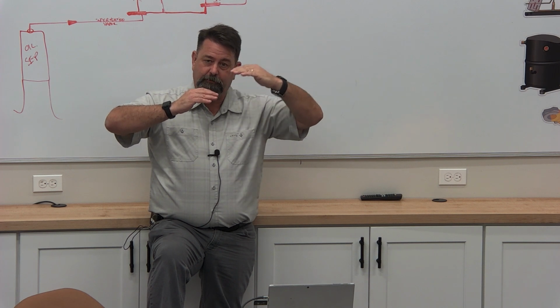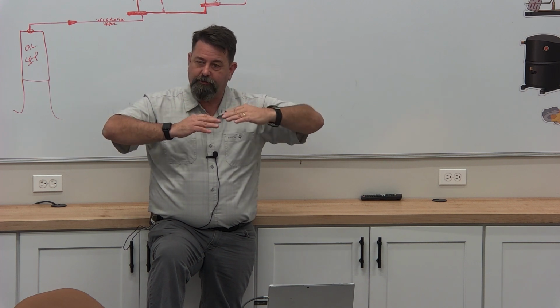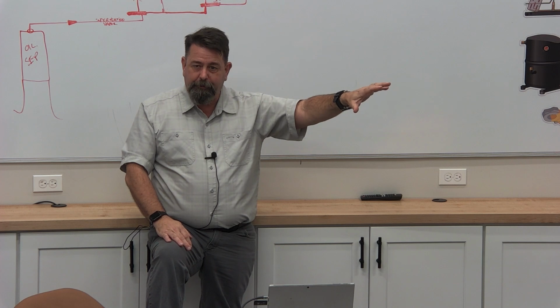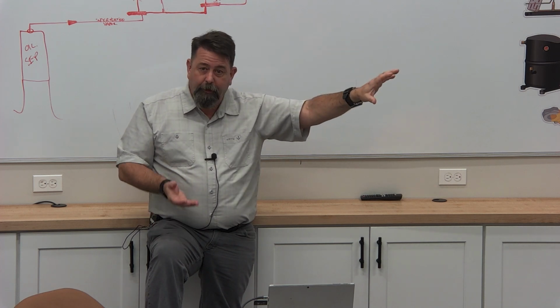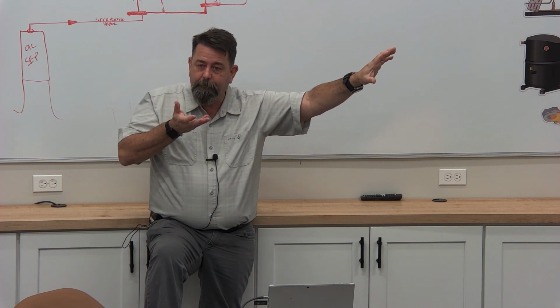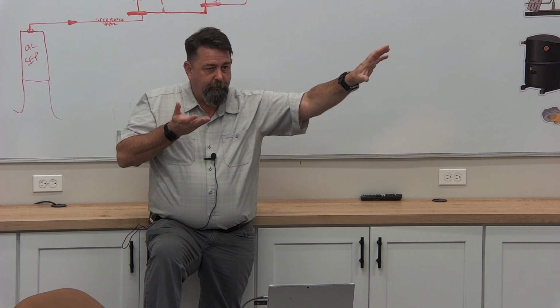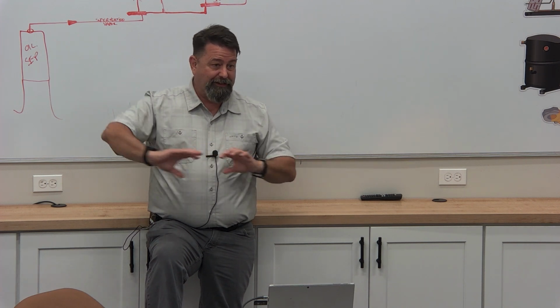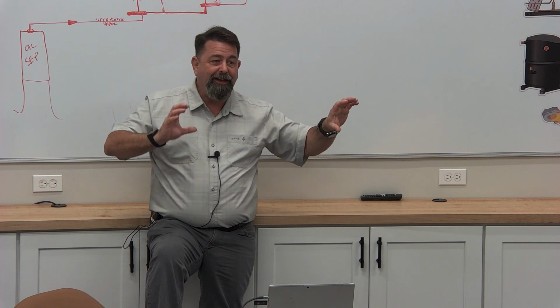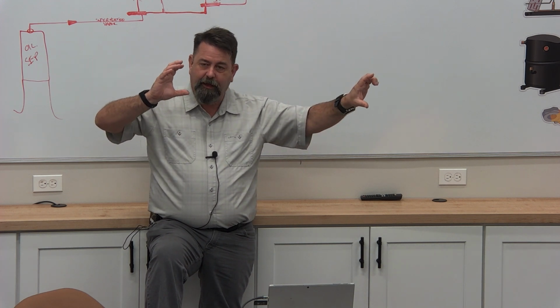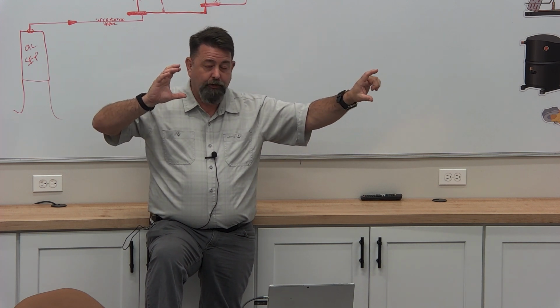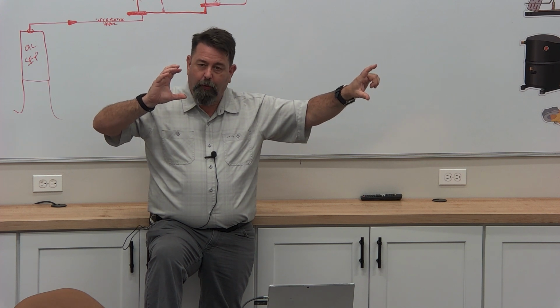That's going to lift it, just like its EPR was holding it. Suction pressure is going to go up. Its EPR is wide open, so its evaporator is also going to go up. It's going to warm up. That means my suction for the entire rack is now floating with the temperature of that case. When that case starts to warm up and gets too warm, I'm going to pull the whole rack back down to cool it down.